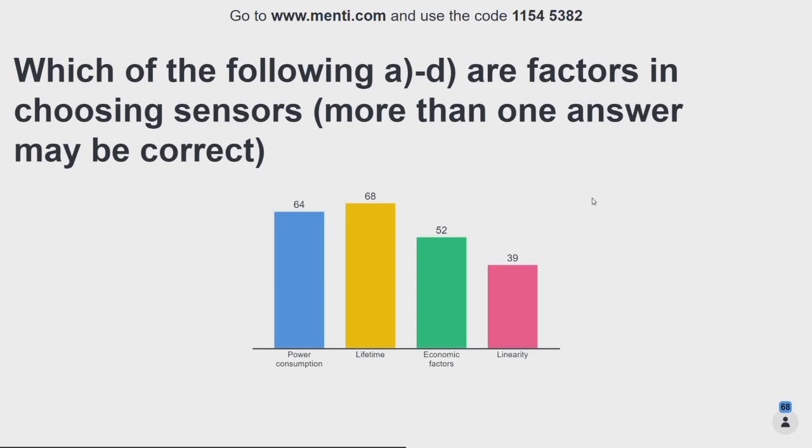Yes, you can compensate, which is the answer that I was just giving. It's a non-linear system, but provided you do an experiment and you can characterize the system performance, then you know what your input is. It's effectively just a lookup table. You measure the output and you've already calibrated it, so you know what the input is, whether that's linear or non-linear. Good question. Really good questions.